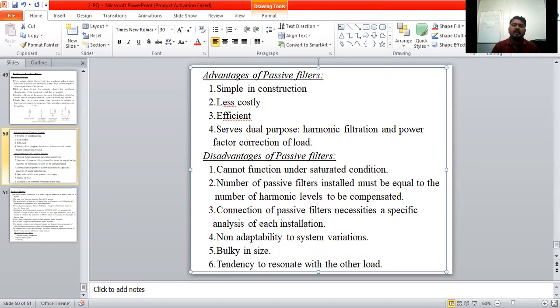See, for each level of harmonics, a different circuit configuration is required in passive filters. So a large number of filters are required. Yes or no? A large number of branches is required for passive filters. Whatever drawbacks there are in the passive filter, we can correct in the active filters. When the number of harmonics to be filtered is large, a large number of passive filters will be required. The actual number of branches depends on the number of harmonic levels.